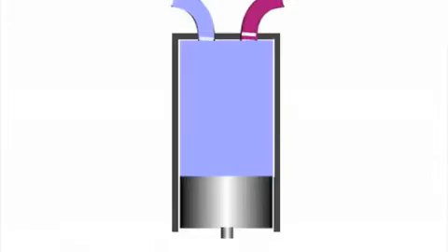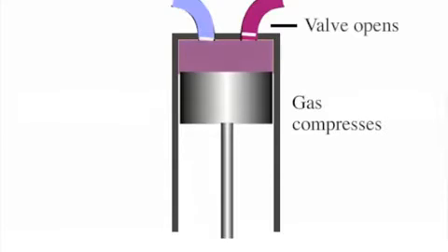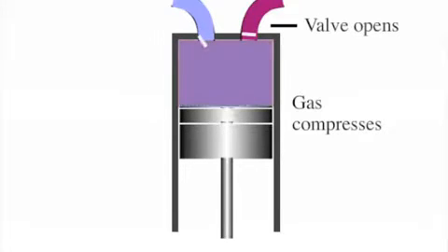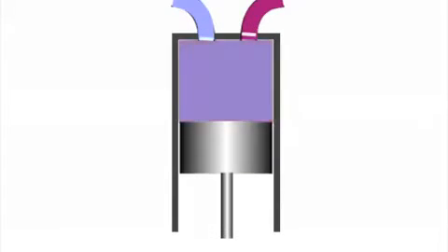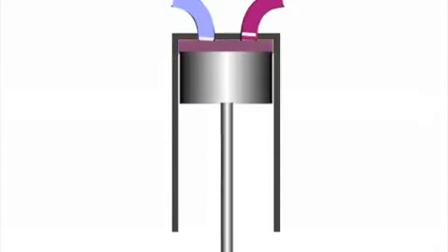In the piston-driven compressor, a piston compresses the gas and an exhaust valve opens when the gas reaches a specific pressure. On the downstroke, low-pressure vapor enters through a check valve. As the shaft turns, the piston begins its upstroke. This causes the intake valve to close.